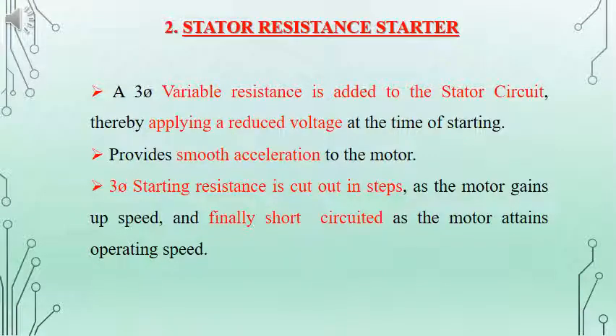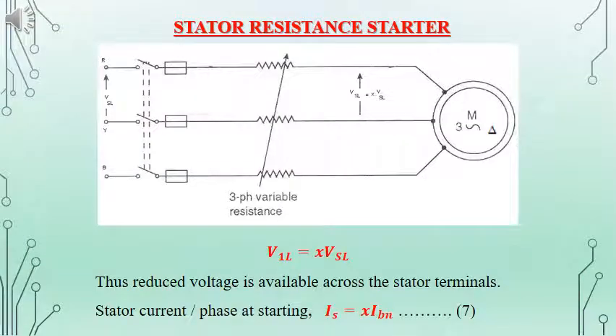Second type of starter is stator resistance starter. Here we will be adding a 3-phase variable resistance along with the stator circuit, by which we will be able to apply a reduced voltage across the stator terminals. That will help to provide a smooth acceleration for the machine. Once the machine picks up speed, we can cut off the resistance in steps. Finally, it will be short circuited, that is, there will not be any additional resistance on the stator circuit for normal operating condition.